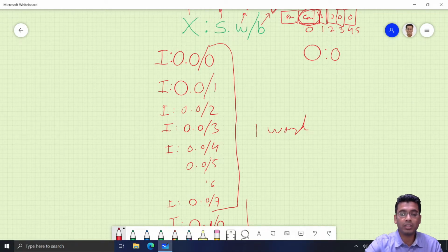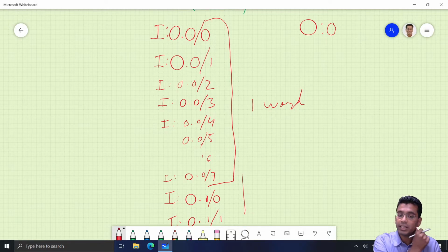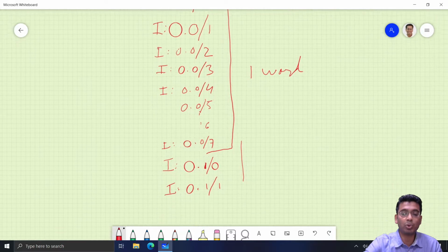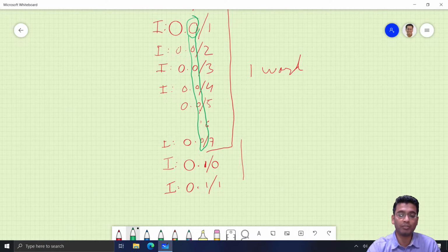Fine. Okay, because I told you digital input takes only 1 bit. And if it is an 8-bit PLC, you can actually incorporate 8 digital inputs in one word. After that, if there are more, then you have to change the word. You see, this column is your words, represented all by 0 word. So the moment your number of inputs exceeded the word limit, you actually switched to word number 1.